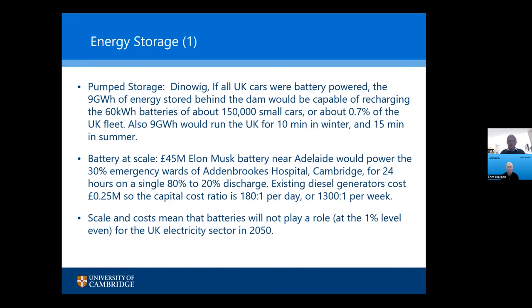At the moment, what they have is 2 diesel generators, which together cost £250,000. So for a day's outage, the ratio of capital cost to provide backup is between 45 million and £250,000, which is 180 to 1. Now, just this last winter, a storm took out the power supply of part of the north of England, a relatively small part, but it was out for a week. If the hospital was out for a week, the capital cost ratio is 1,300 to 1. No engineer with any ounce of professional integrity would recommend investing with those odds.